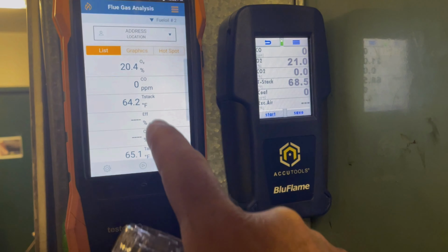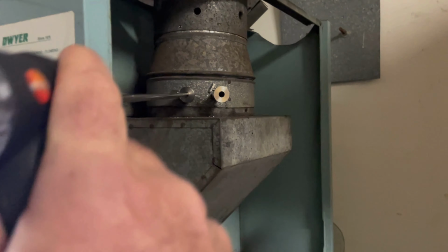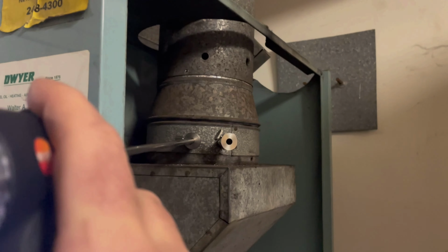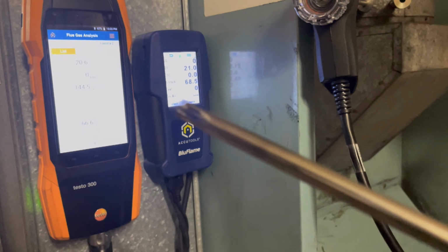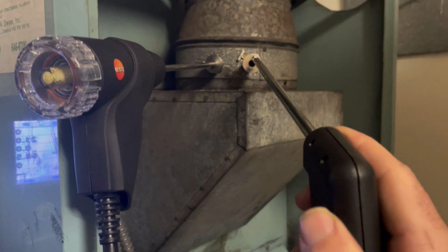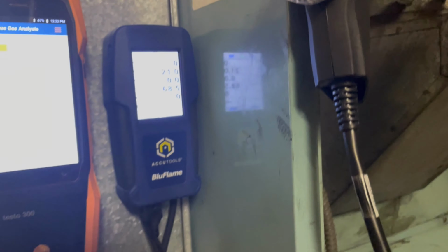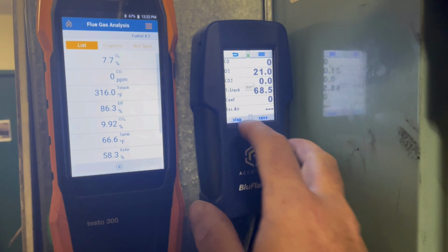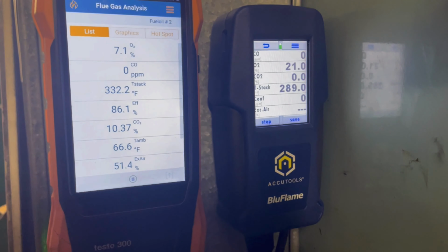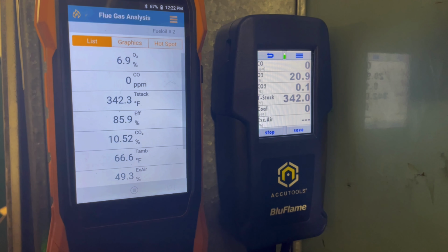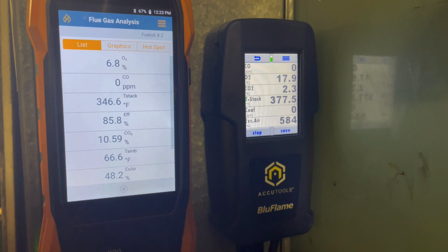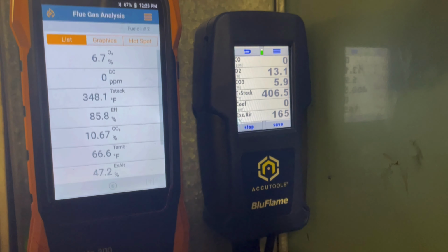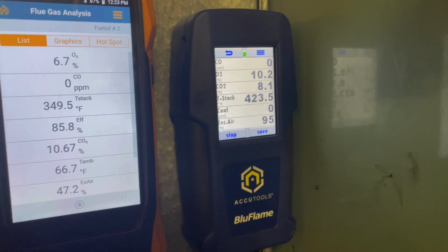For the Testo, you have to zero it out before you insert the probe, so I just went ahead and did that. Up next is the BluFlame probe. I'm trying to get the insertion depth about the same to give us some more accurate results between the two analyzers. I'm going to go ahead and press start on the BluFlame. The Testo has a little head start here. And being that it's an oil furnace, the first value that typically oil guys concentrate on is the CO2 number.